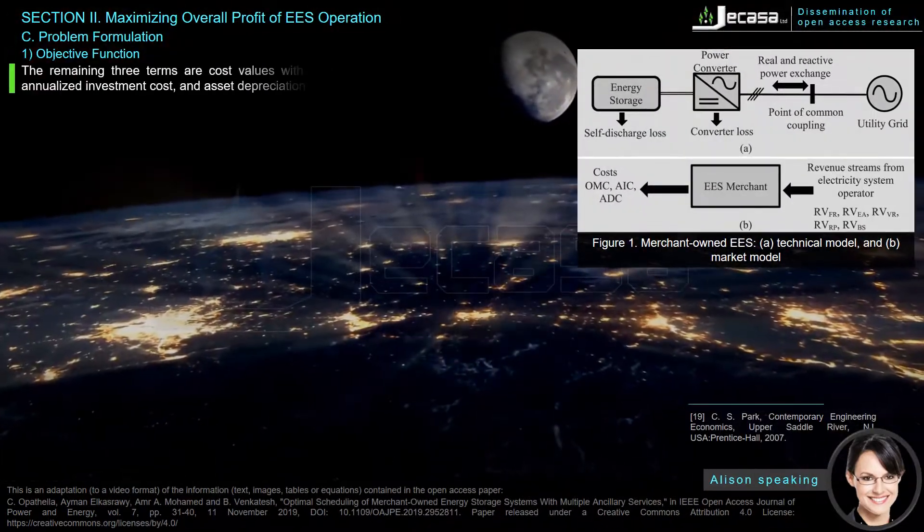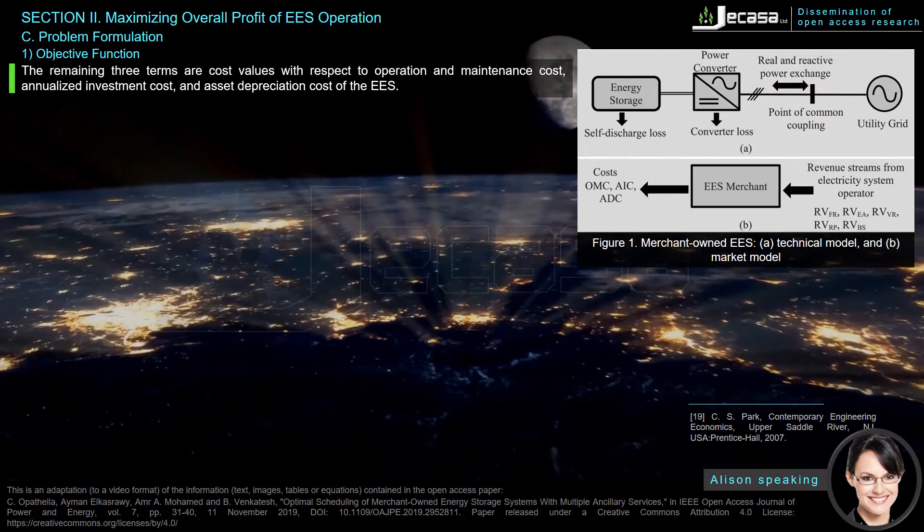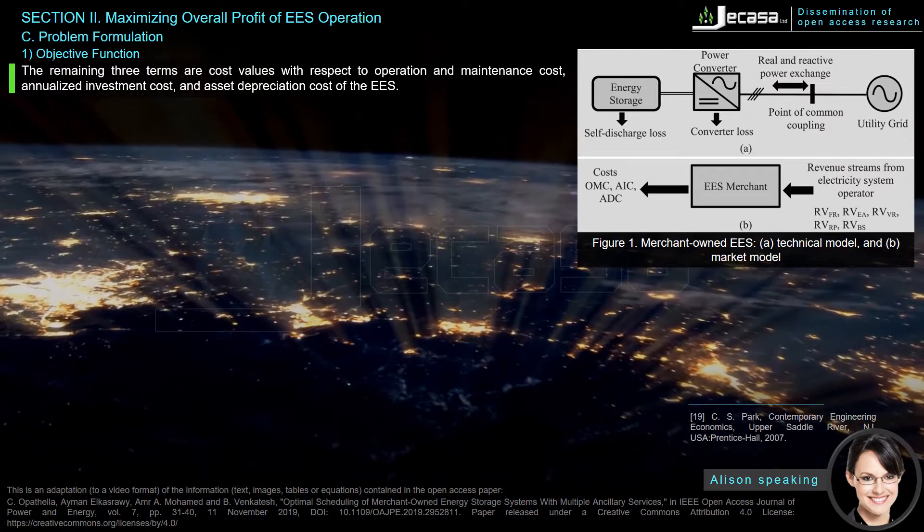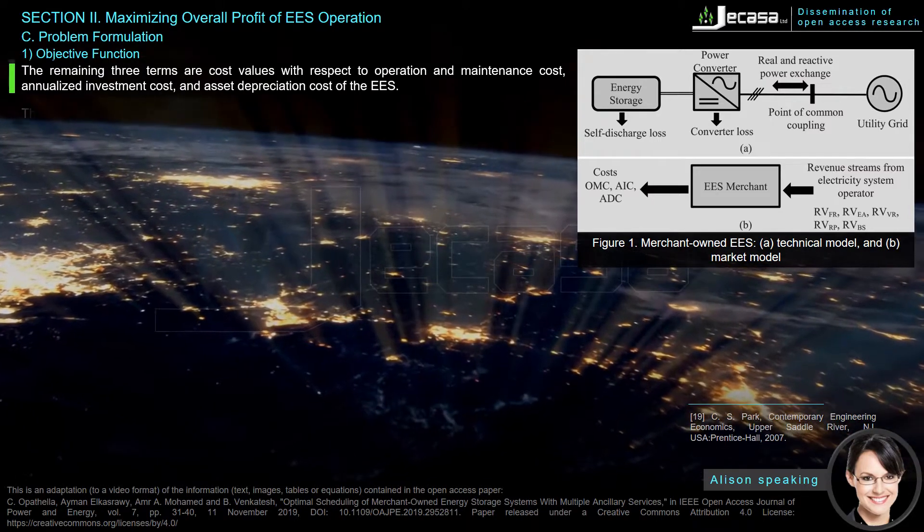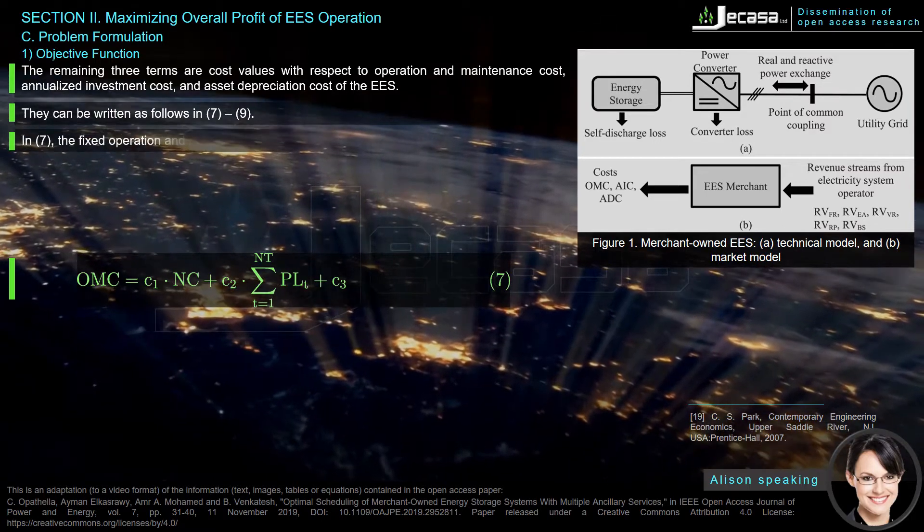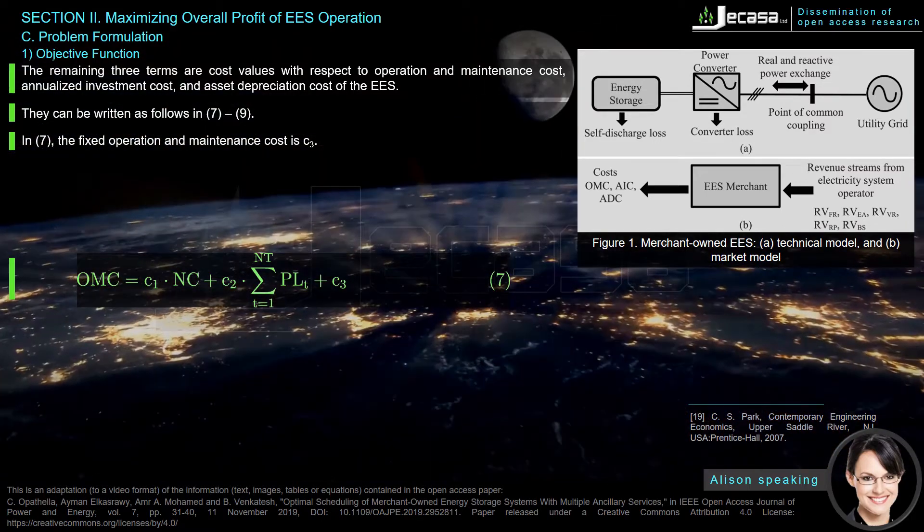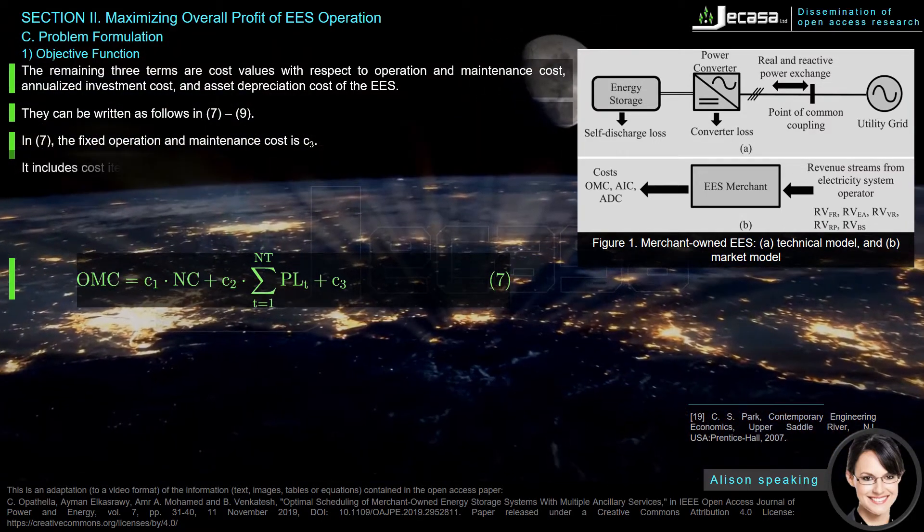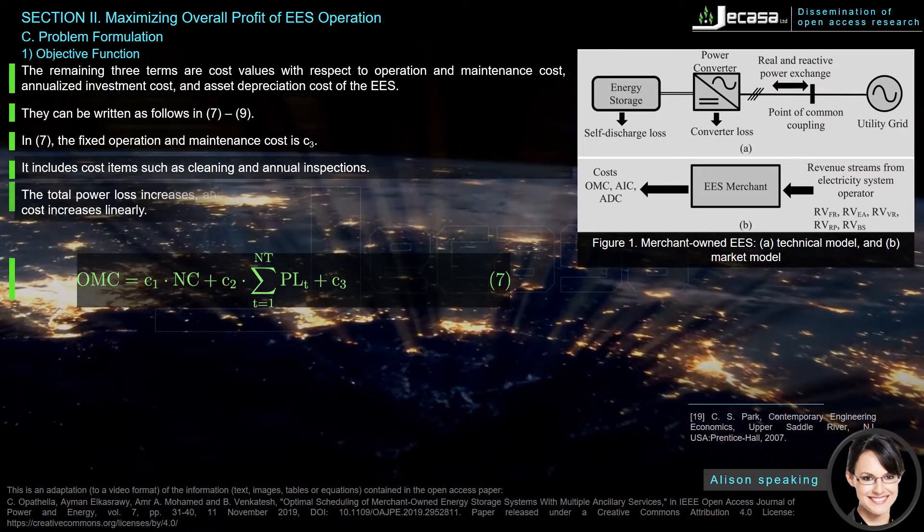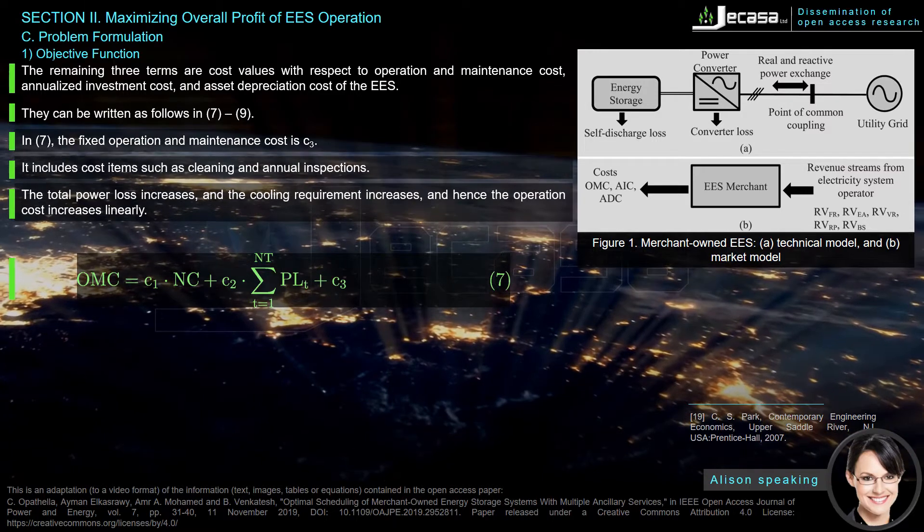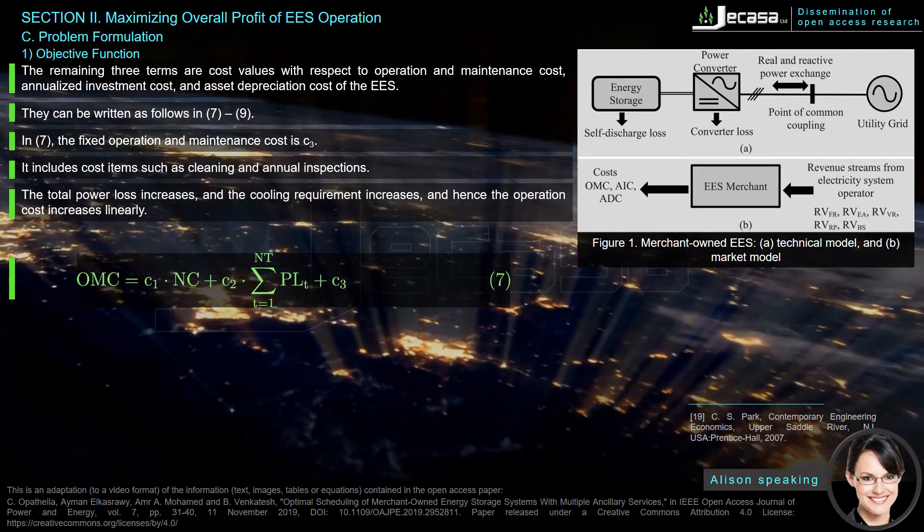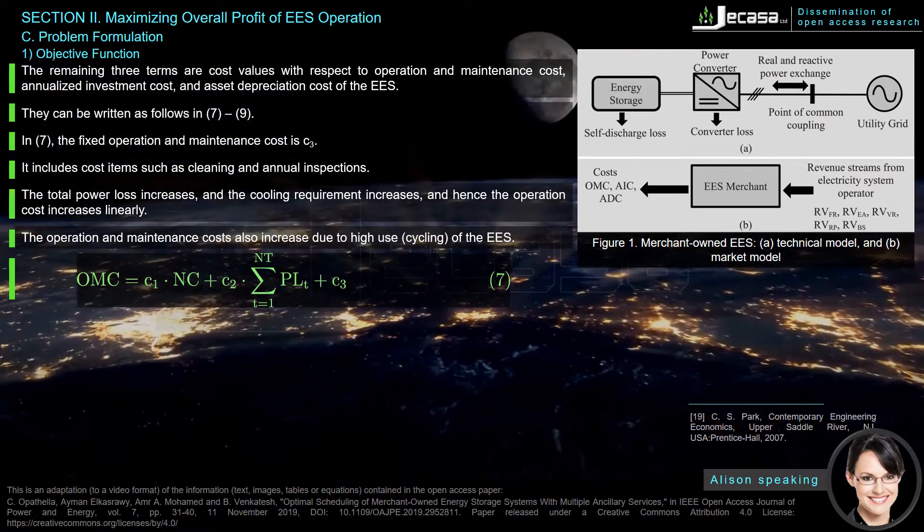The remaining three terms are cost values with respect to operation and maintenance cost, annualized investment cost, and asset depreciation cost of EES. They can be written as follows in equations (7) through (9). In (7), the fixed operation and maintenance cost is C3. It includes cost items such as cleaning and annual inspections. The total power loss increases and the cooling requirement increases, and hence the operation cost increases linearly. The operation and maintenance costs also increase due to high use cycling of EES.